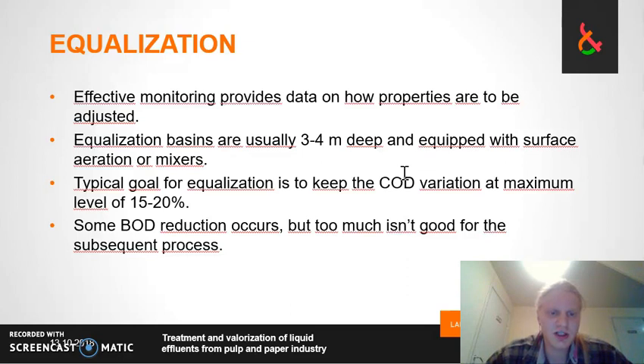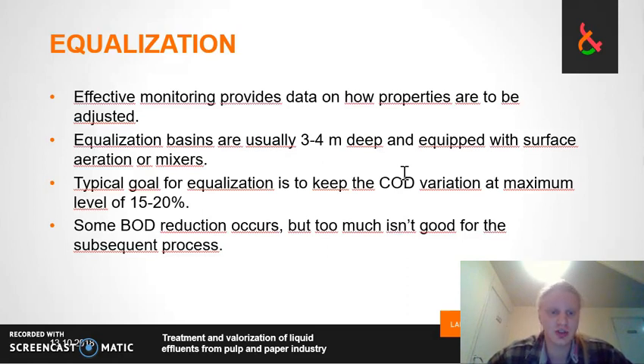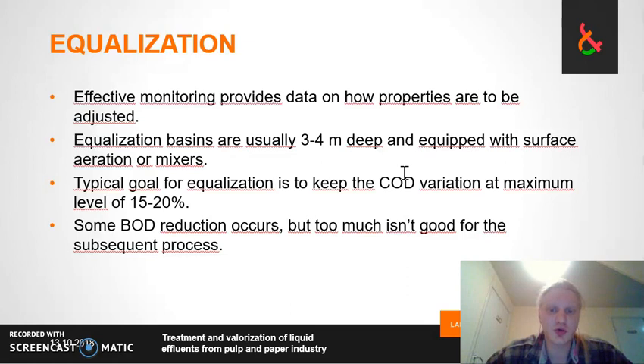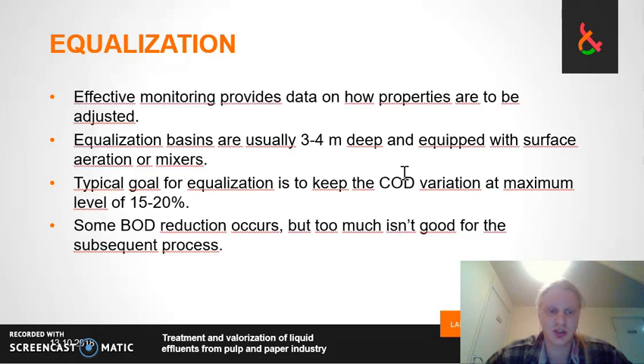These equalization tanks have goals. The goal is to keep the output as stable as possible. An example of such a goal could be keeping the COD variation at a maximum level of 15 to 20%.